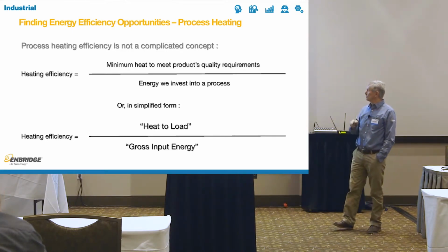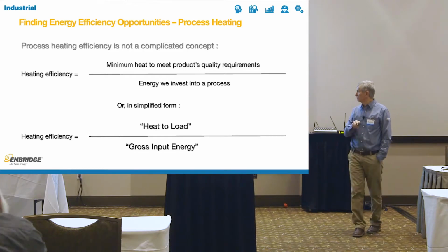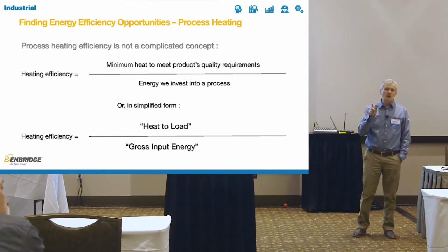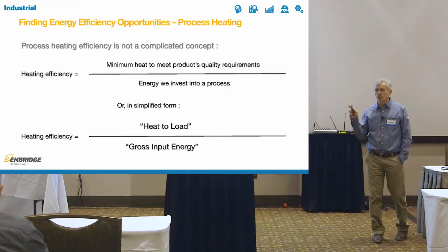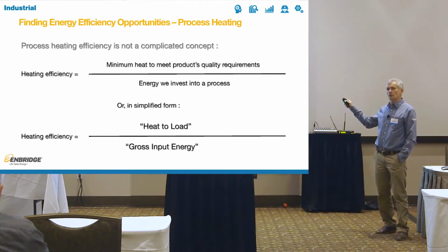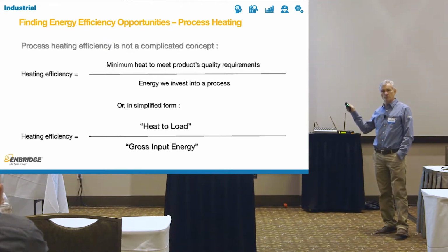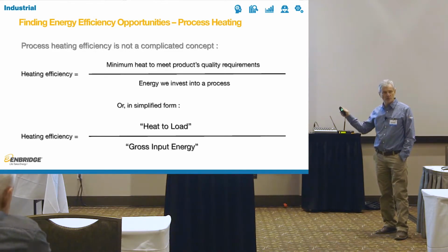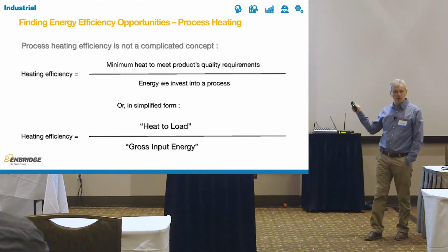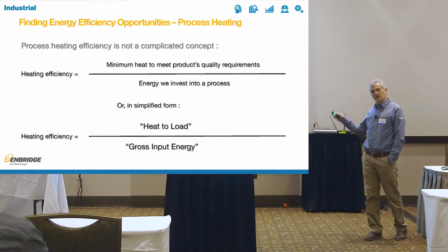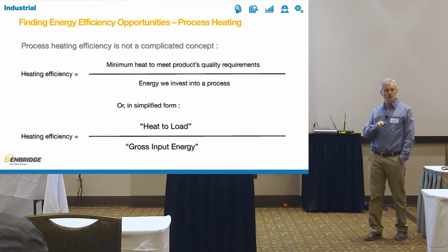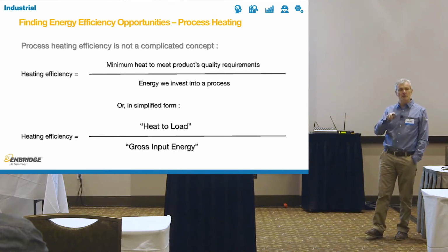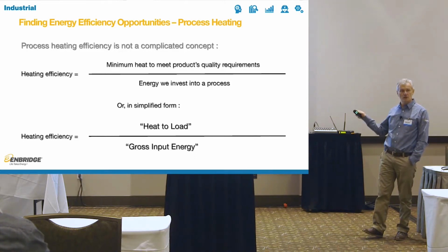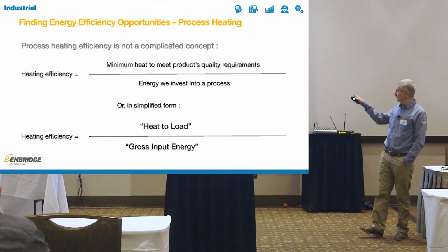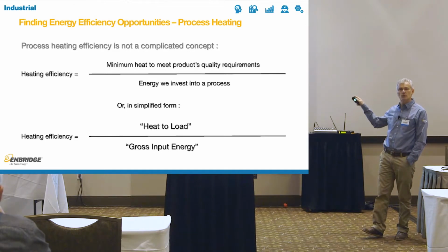So if we reduce the energy we invest into the process, we will increase our heating efficiency, and you will notice that we're not touching the heat to load. Everybody is always very careful, very justifiably, not to affect their process. None of the things that we suggest will actually affect your process. Your process will remain the same. What will be affected is the losses along the way. You will put less energy into the system and still get the same heat to your load.